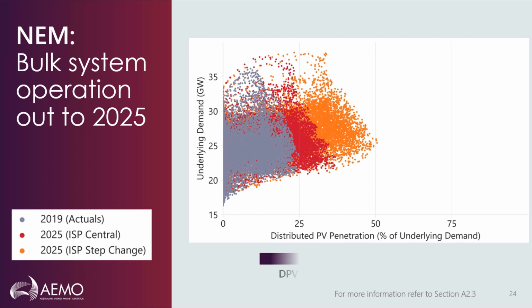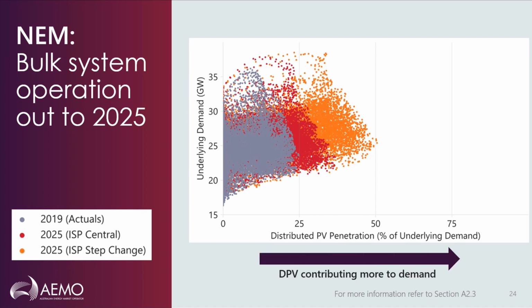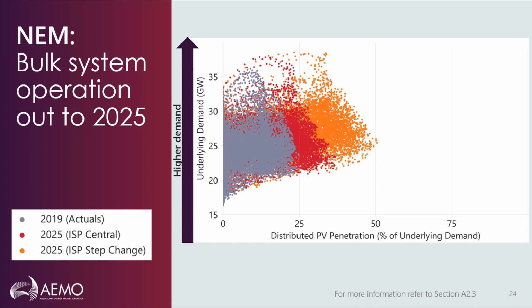On the x-axis, it shows the instantaneous DPV penetration against demand. So as we move along to the right, it means that more DPV is contributing to meet demand, and where many of the challenges will arise. On the y-axis, we show what the underlying demand is. So as we move up along the axis, it shows increasing demand. The dots represent a half-hour period within each year and therefore compare the scatter of potential DPV contribution against underlying demand.